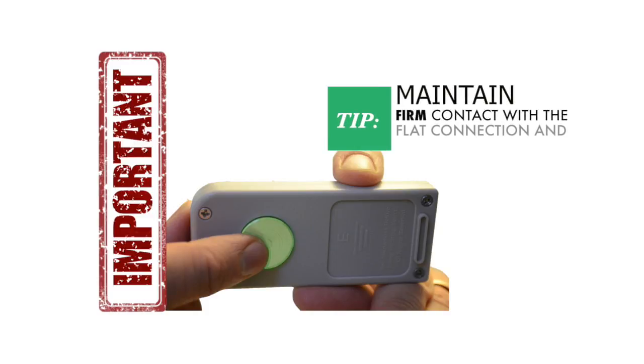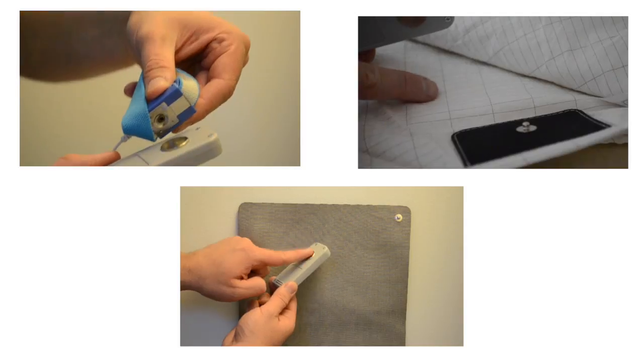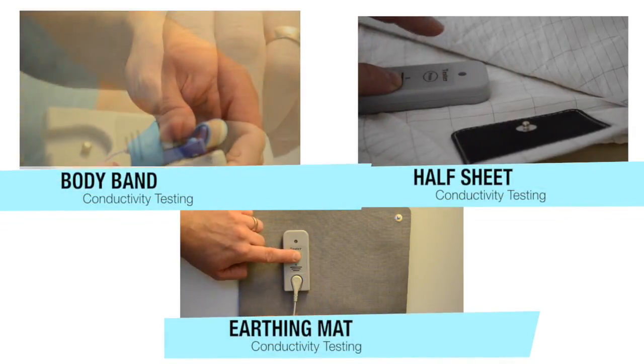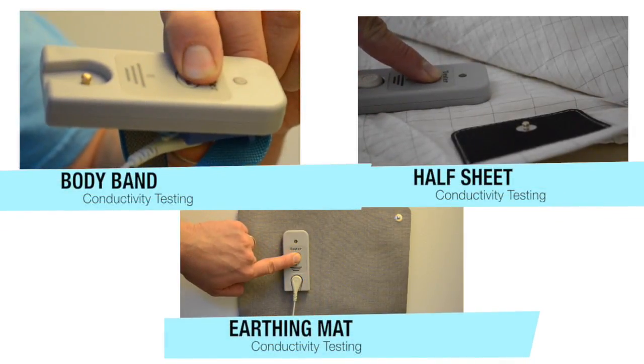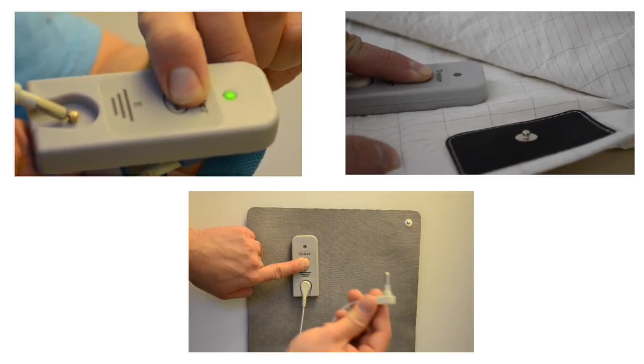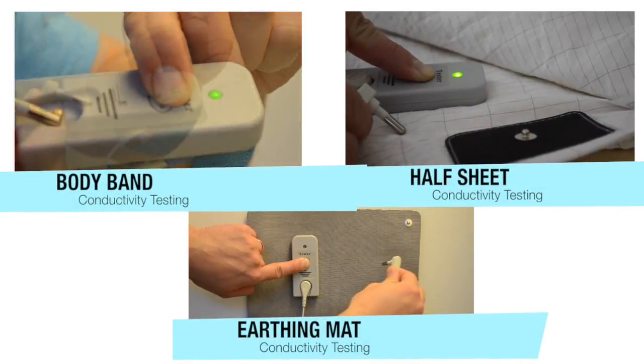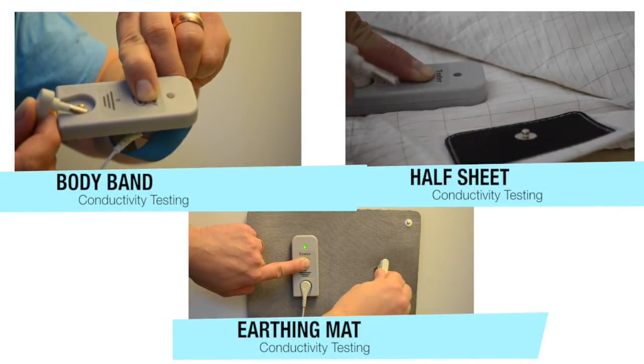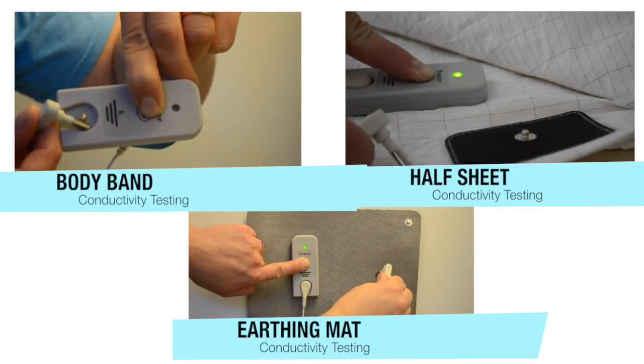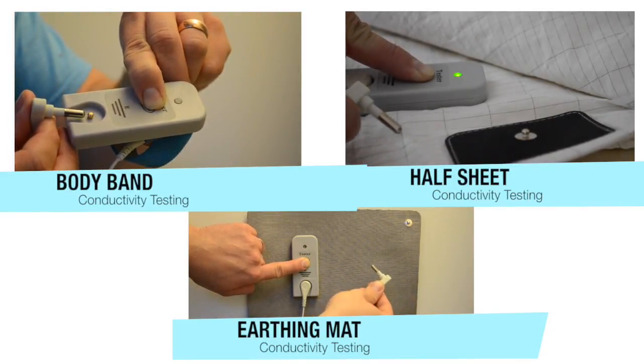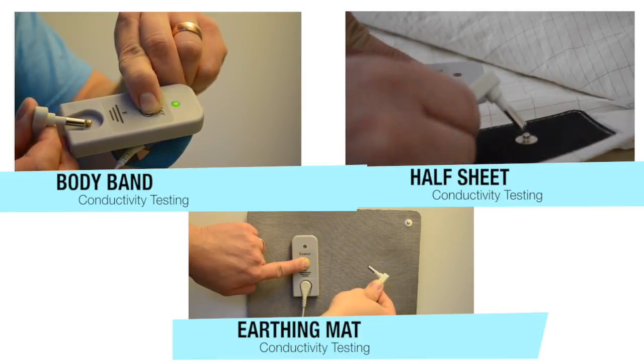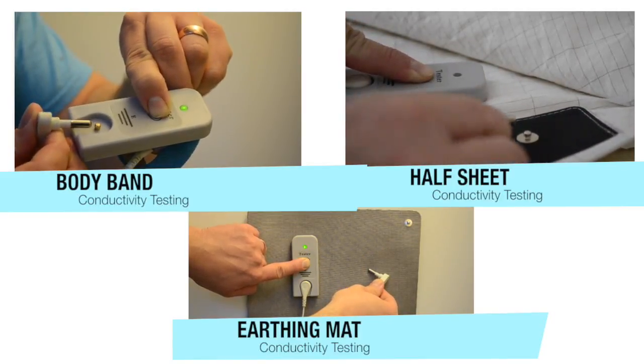This is important. You will need to ensure direct contact is maintained between the tester and the earthing product to test accurately. With the tester in place, press and hold down the button and the green light will flash once. Maintain this position and be sure to continuously hold the button down firmly. With your other hand, touch the male connection on the grounding cord to any part of the conductive surface on the earthing product while still holding the button down. Once again, the green light will come on if there is total conductivity because you have completed the circuit by adding the earthing product to it.